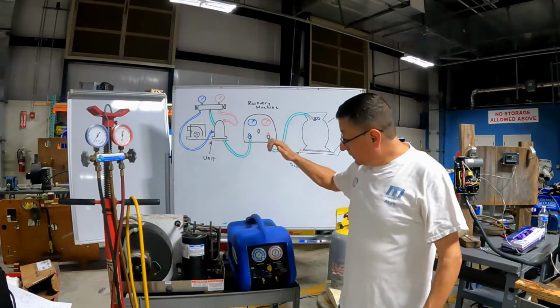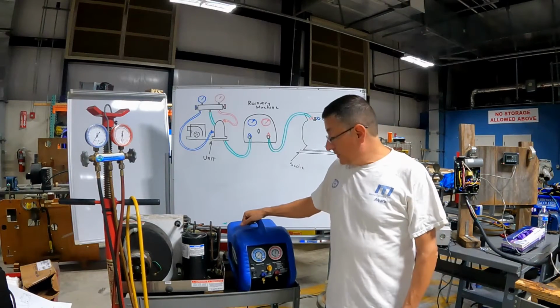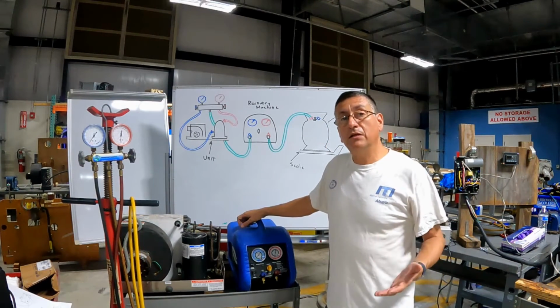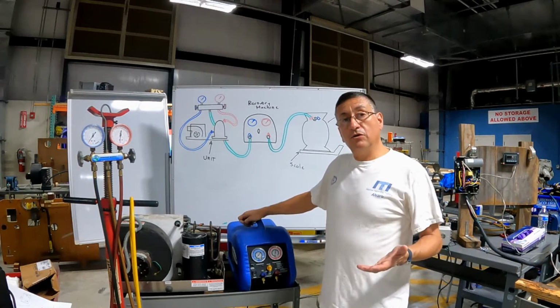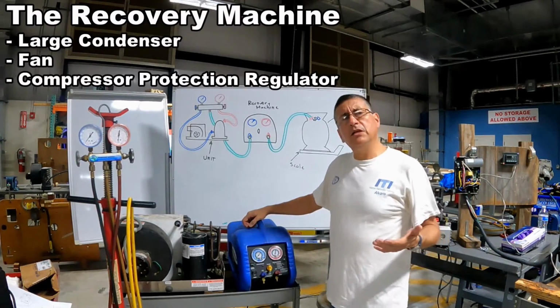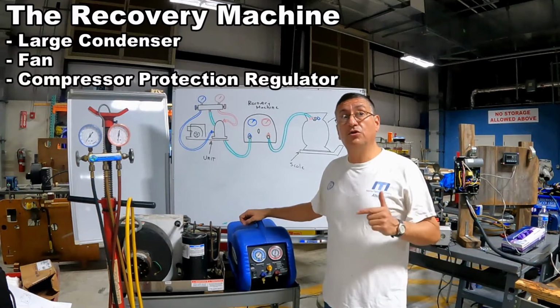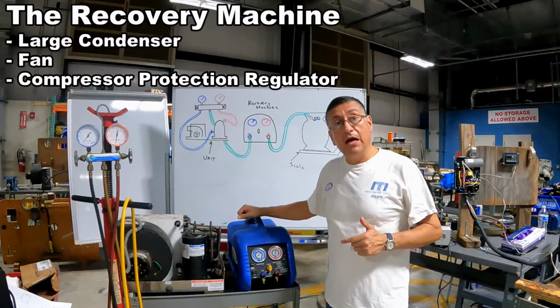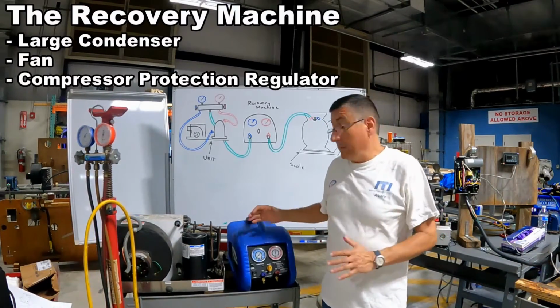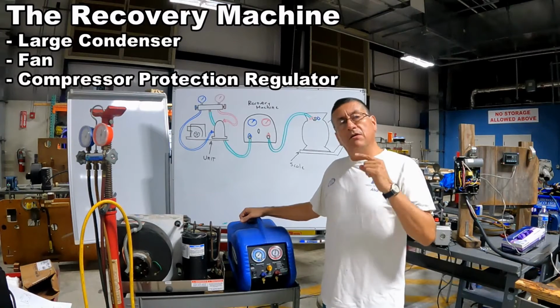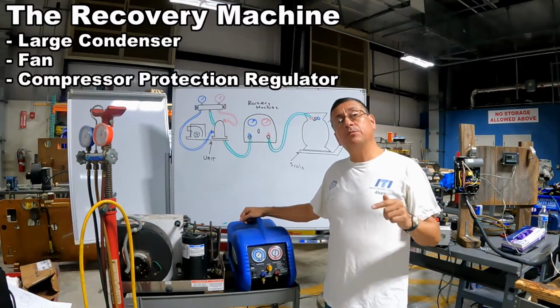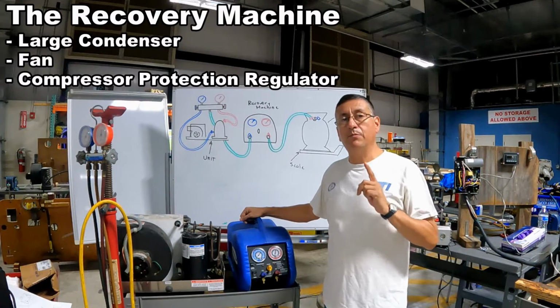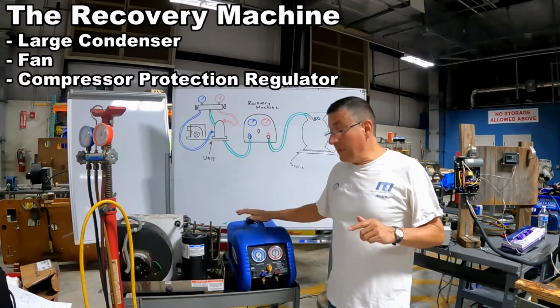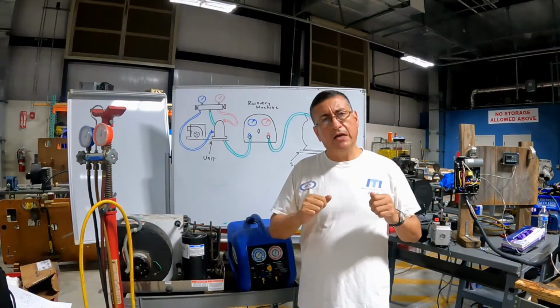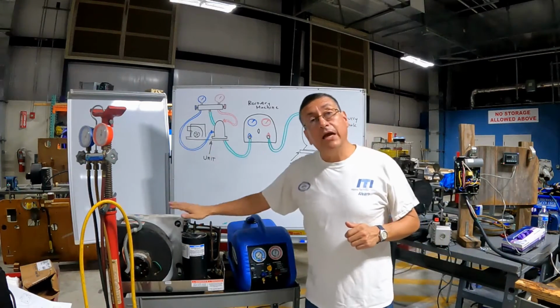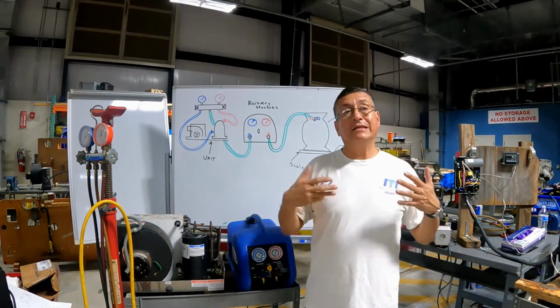And also we need this unit, the recovery unit. This is a special unit designed to recover the refrigerant in air conditioning equipment. Internally, this unit has a large condenser, a fan, and a compressor. It's like an air conditioning equipment integrated. Condenser, fan, and compressor. Additionally it has a compressor protection regulator, that's an important element. And it also has a high pressure cutoff switch to protect the equipment in case the pressure passes the limit.